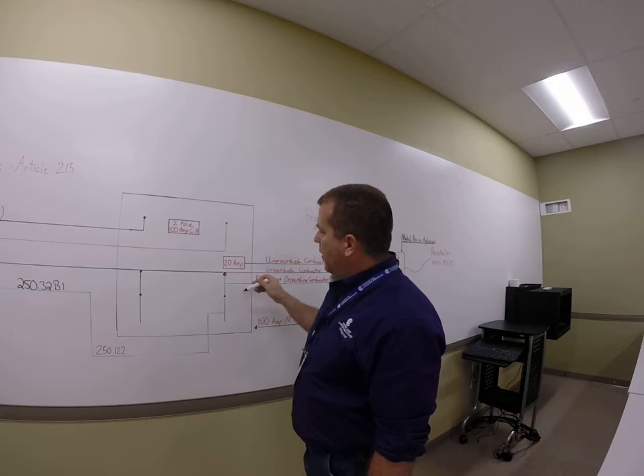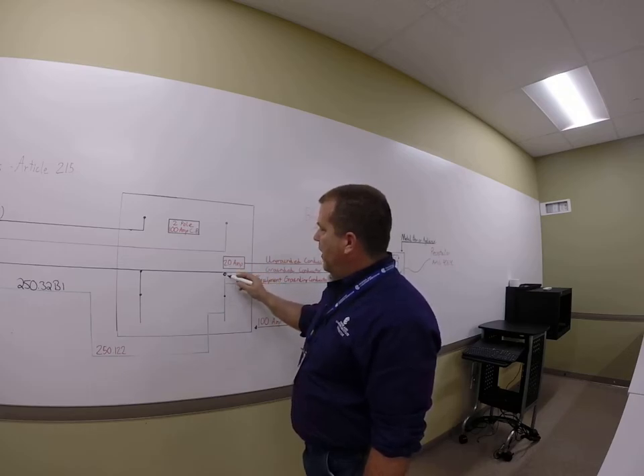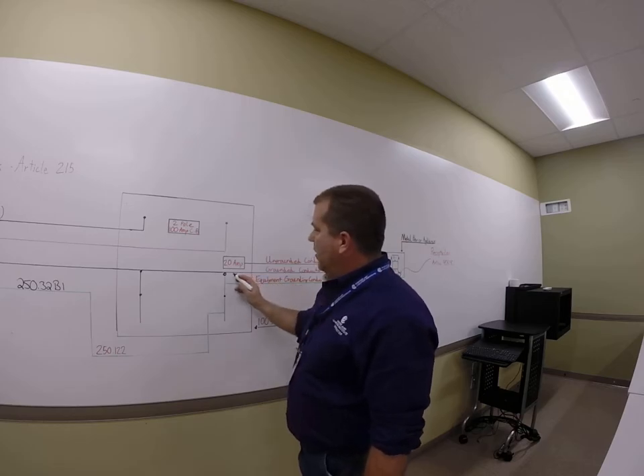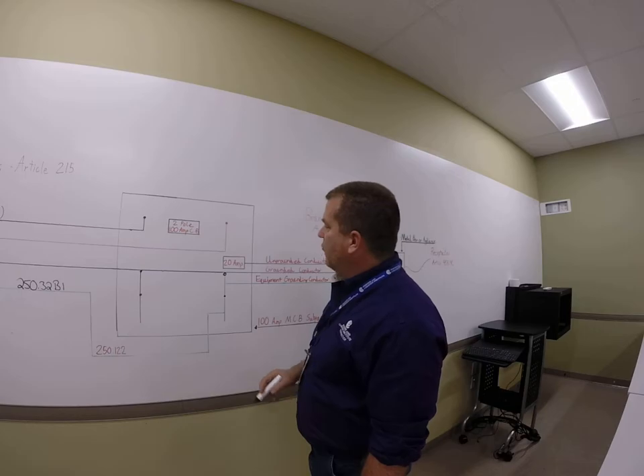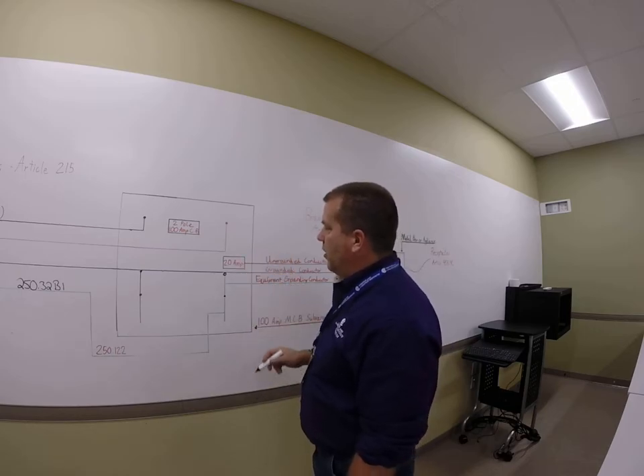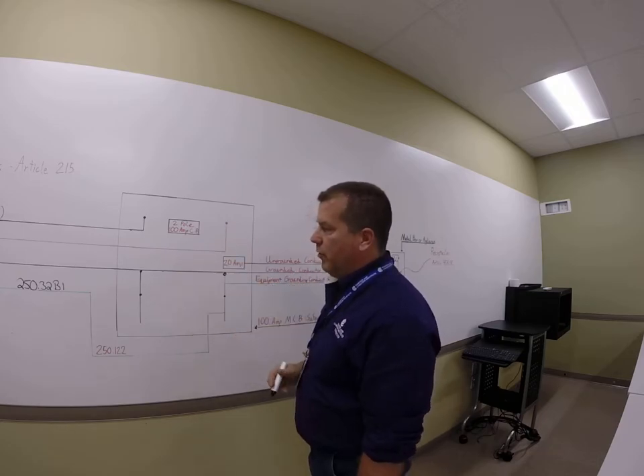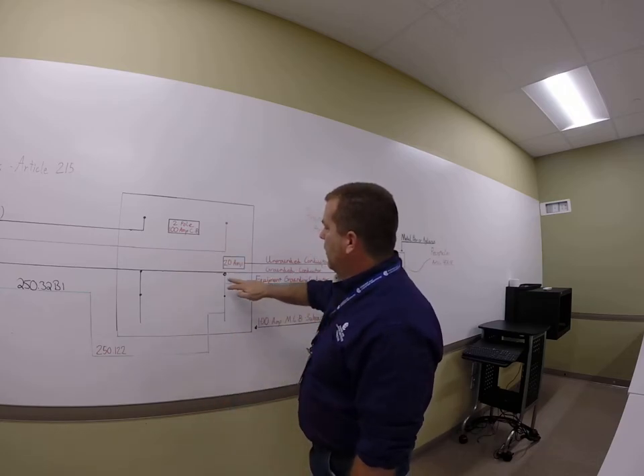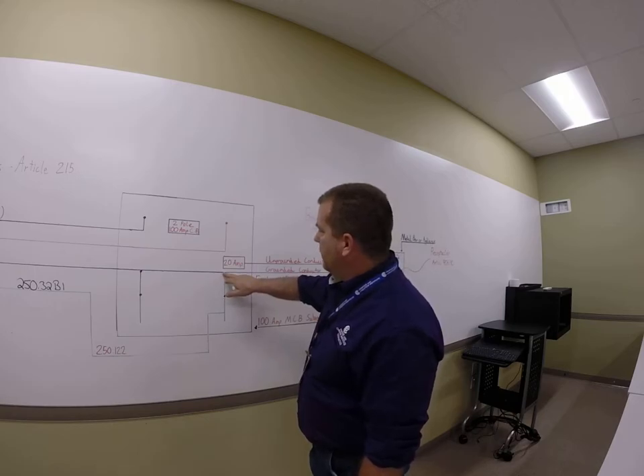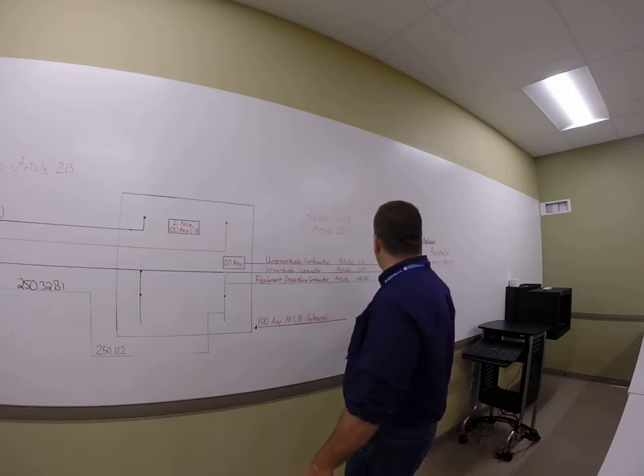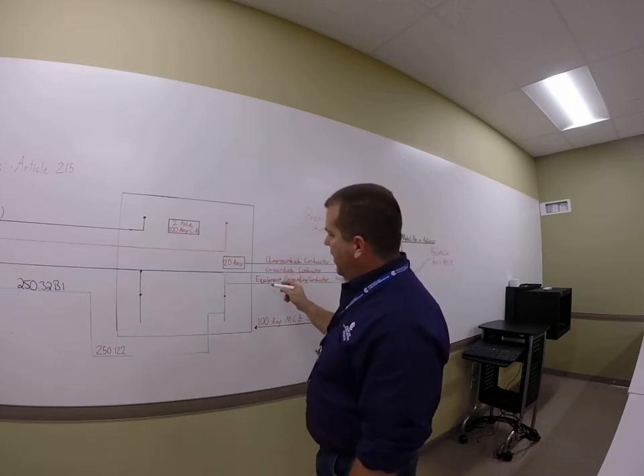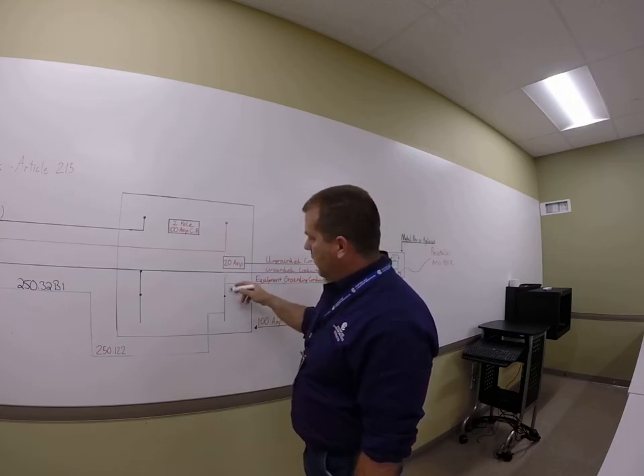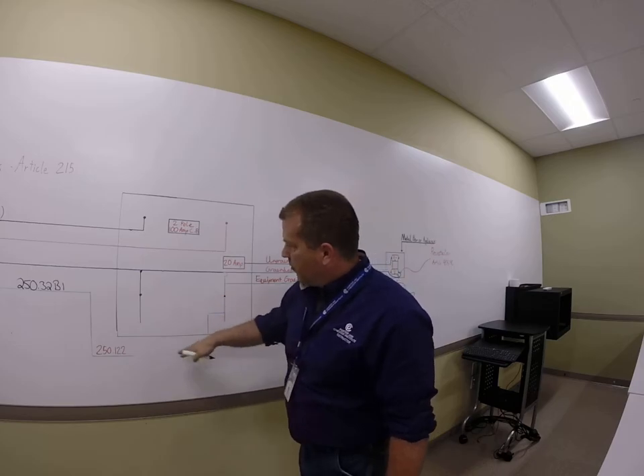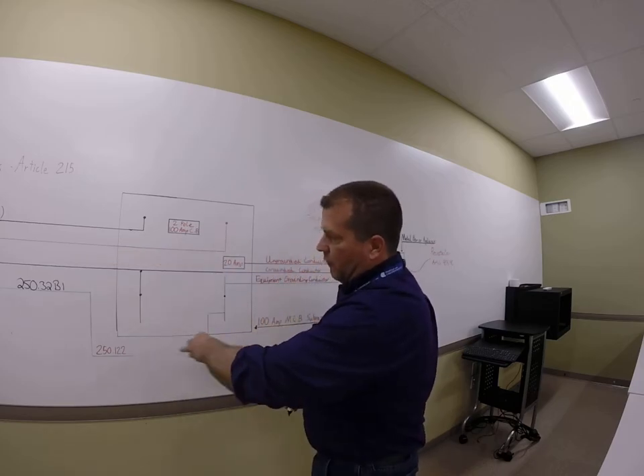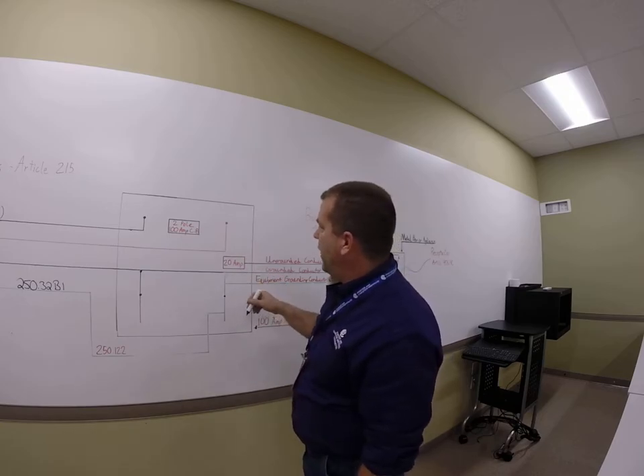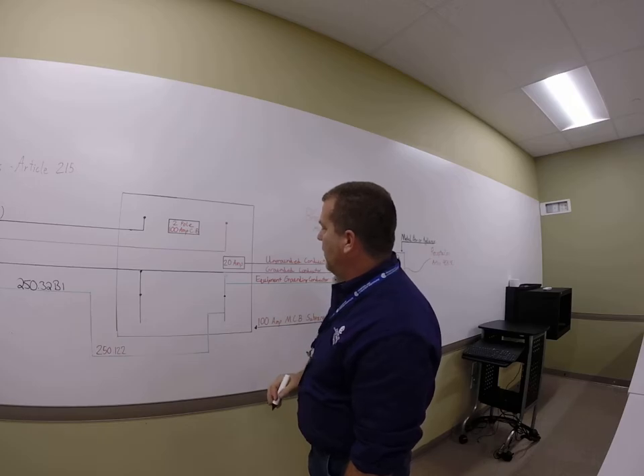So what ends up happening here is I'm going to have ground current come over here, and if I use the main bonding jumper here, I incidentally created a parallel path where I'm now putting fault current on the grounded circuit conductor. That could be dangerous because you could be feeding that fault current back on some other piece of equipment through the neutral, and you could be frying that piece of equipment. So let's get rid of that main bonding jumper for a second. And now look, if I have fault current coming on my equipment grounding conductor, I have a path of least, there's no resistance here because I'm connected completely all the way back to the source. So that current's going to flow unimpeded. It doesn't pick up a parallel path, and it allows this overcurrent device to open instantaneously.